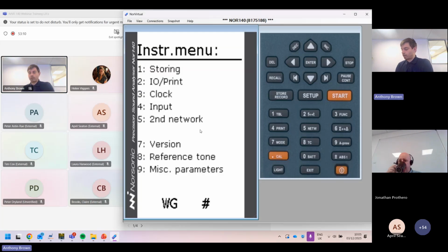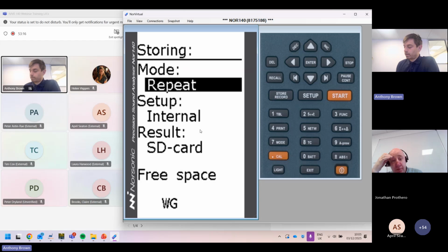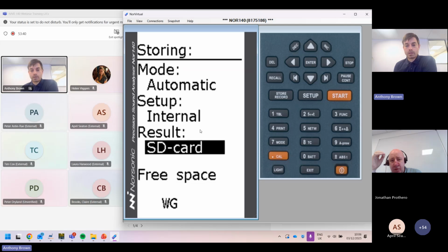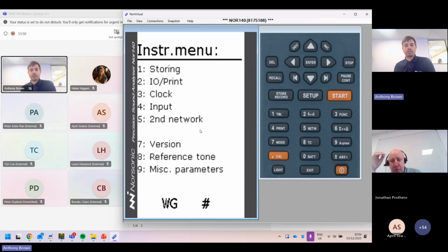Okay, so hopefully everyone's got their clock set up. I've just answered the couple of questions we had about storing. You don't need to go into this menu. You will have found there were some more options in here, but to be honest, just stick to the automatic and repeat. Don't use the other options because they will affect how the meter runs for noise nuisance. Those other options are for manually starting and stopping it at your own pace. Results need to go to the SD card because there's not much internal memory, maybe just a few megabytes. So I just press enter to go back. I'm now in the instrument menu. We've just done the clock.